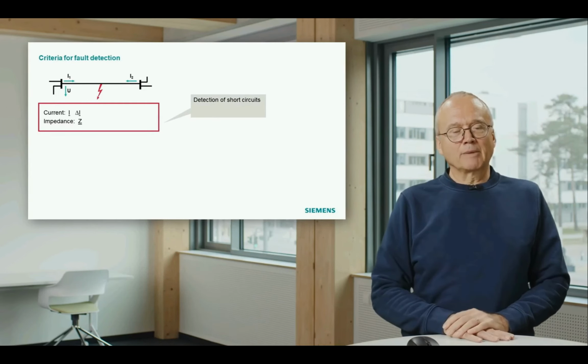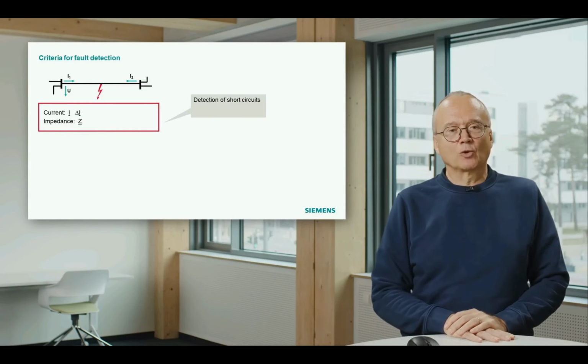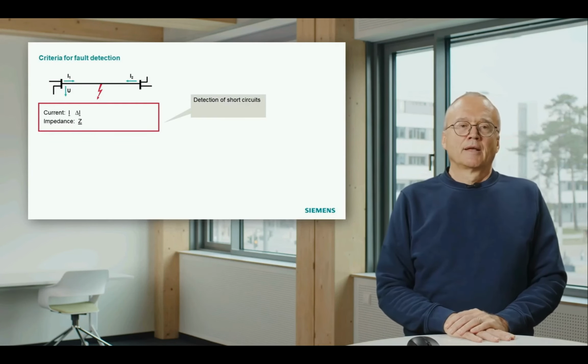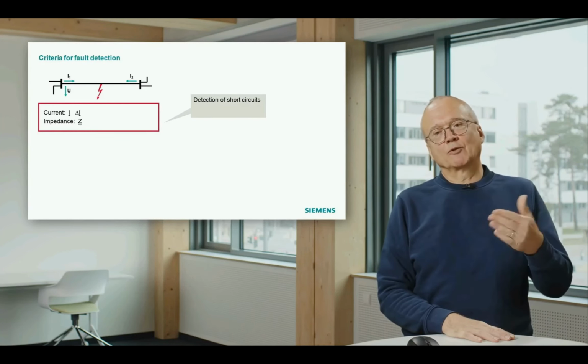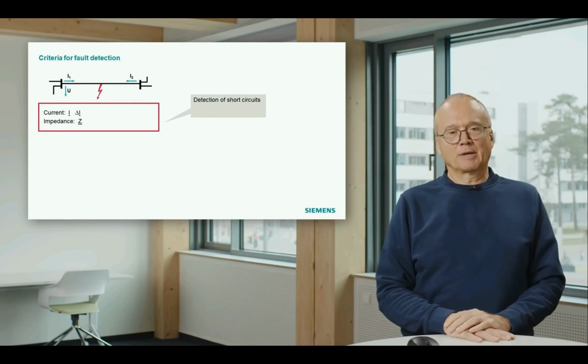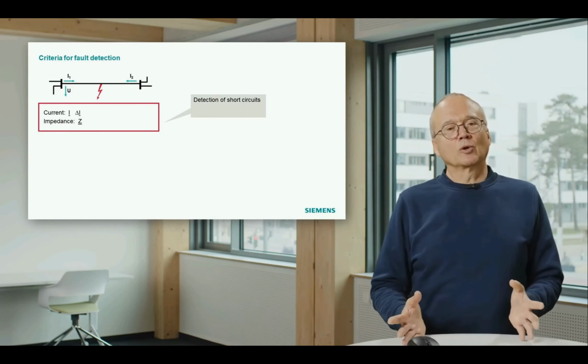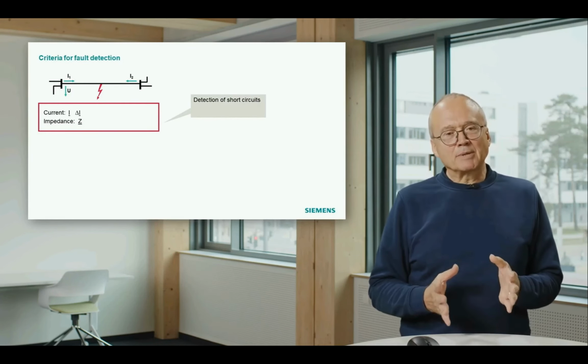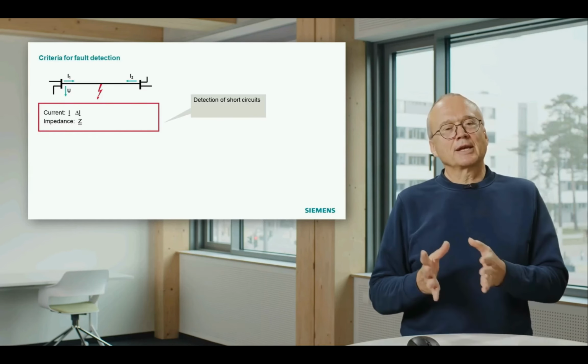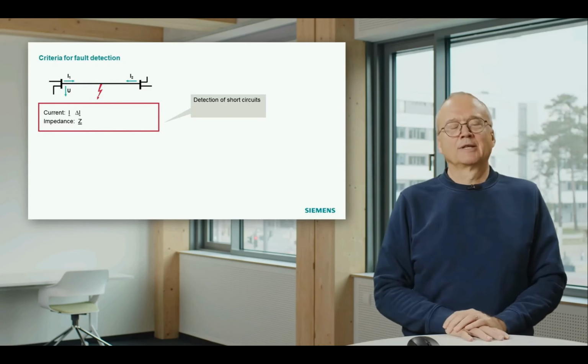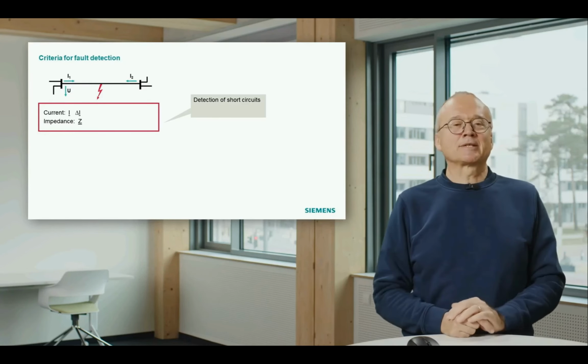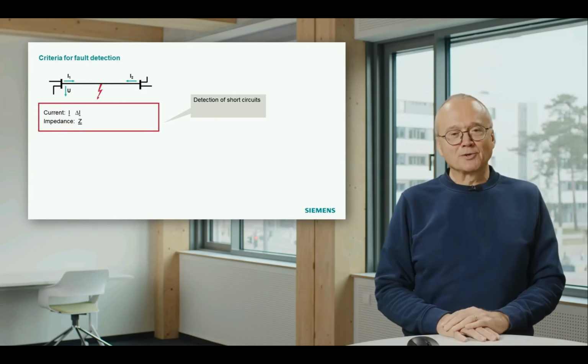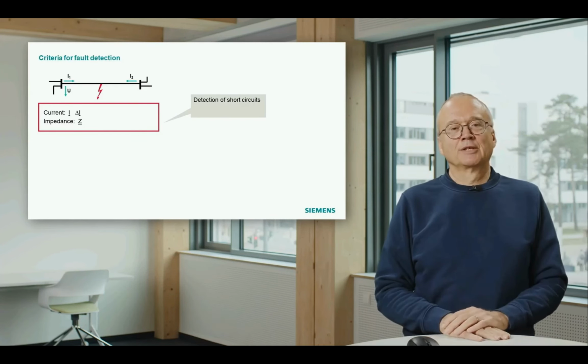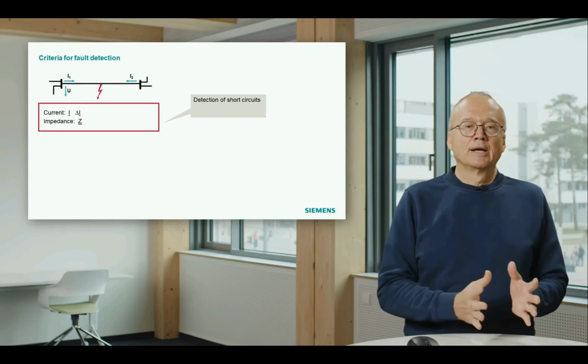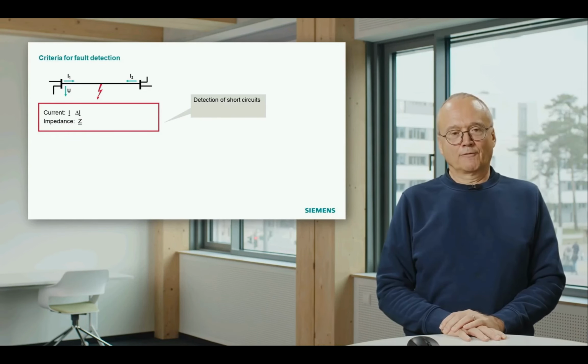The next one I would like to mention is protection which is based on the impedance. That means we measure the impedance. To get the impedance, we have to measure the voltage and the current. If we divide the voltage by the current, we get the impedance. And we will also see, based on the impedance, we can make a decision: is there a short circuit on the line or not? Protection based on the impedance is normally not called impedance protection, it is called distance protection, because the impedance is somehow a criterion for the distance of the fault.